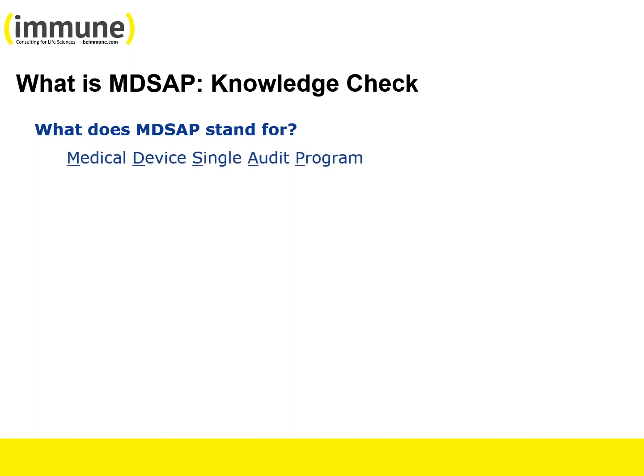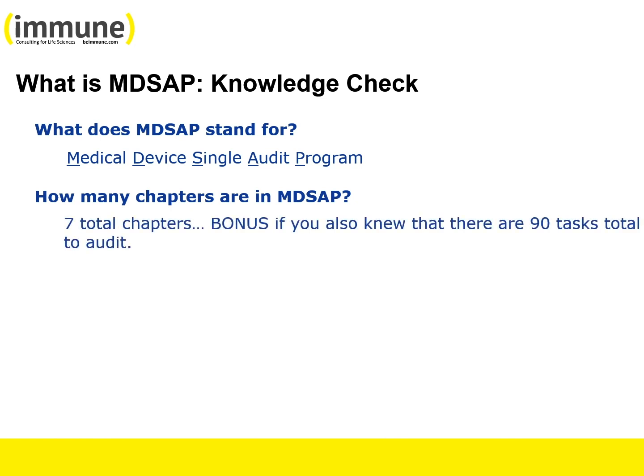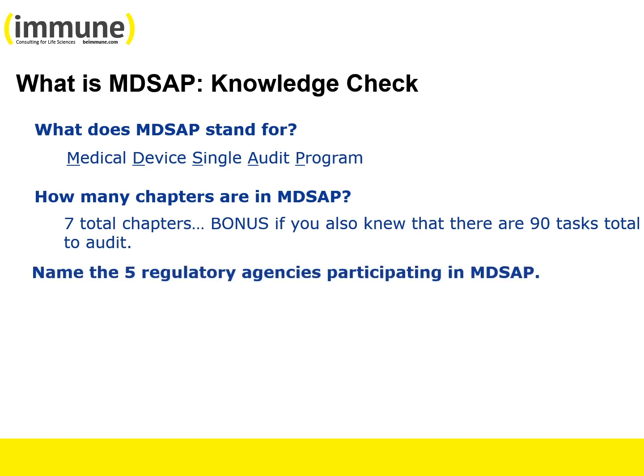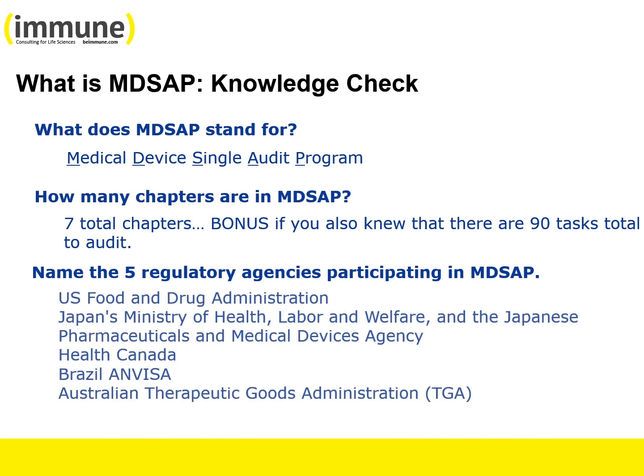Now we're going to test your knowledge. What does MDSAP stand for? The Medical Device Single Audit Program. How many chapters are in MDSAP? 7 total chapters, and a bonus if you also knew that there are 90 tasks. Name the 5 regulatory agencies participating in MDSAP. The U.S. Food and Drug Administration, Japan's Ministry of Health, Labor and Welfare, and the Japanese Pharmaceuticals and Medical Devices Agency, Health Canada, Brazil Anvisa, and Australian Therapeutic Goods Administration.